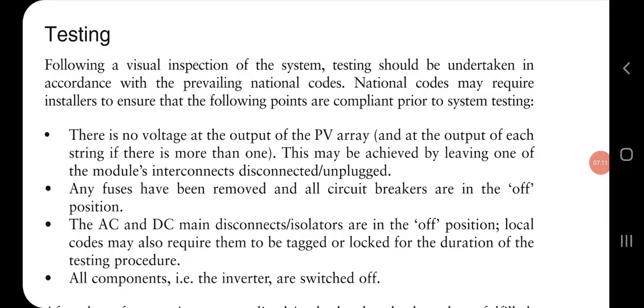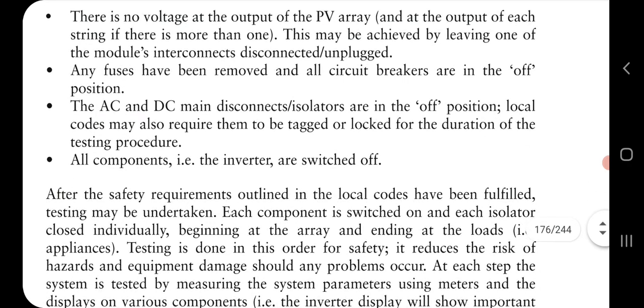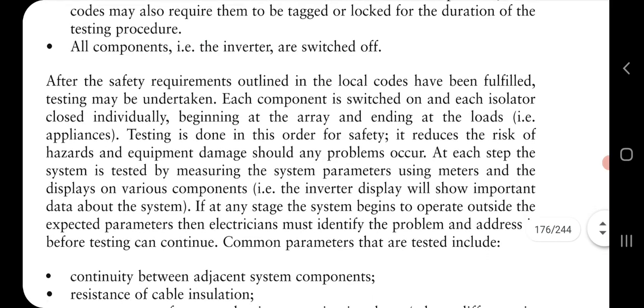Testing has to be done for the PV system, and there are many national and local codes which have to be followed. For this, there should be no voltage at the output of the PV arrays, and everything has to be disconnected. Any fuses have to be removed. The circuit breaker should be off. The AC and DC main disconnectors should be in the off position, and the inverter also should be in the off position. Safety plays a very important role in this one.